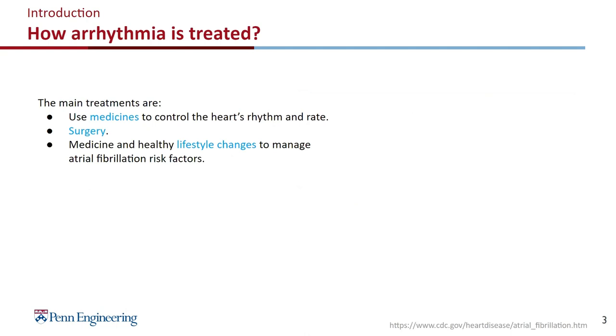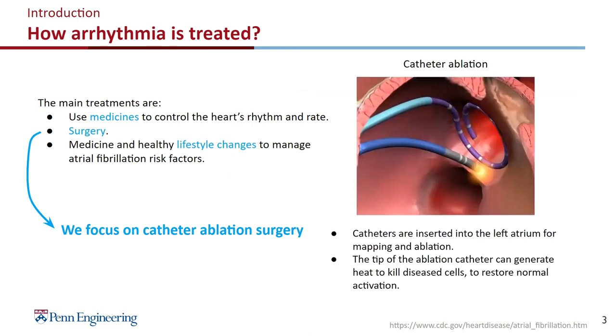There are several treatments. The major ones are medicine, surgery, and lifestyle changes. We focus on catheter ablation surgery. During the surgery, catheters — which I'm showing in my hand here — are inserted through the vein to the heart. This is a mapping catheter; it has electrodes on it and it records endocardium electrograms. Based on that information, physicians go in with an ablation catheter. The tip of the ablation catheter generates heat to kill abnormal cells and restore normal activation.